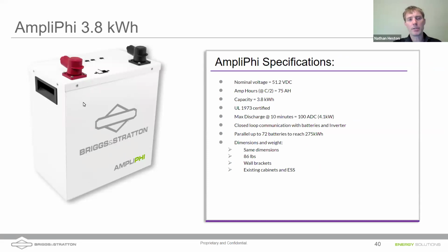This is our AmpliPHI battery. It's got that more sophisticated communicating BMS that's in there, allowing you to communicate with compatible equipment like a Solar inverter or a Briggs Stratton inverter. It's got the integrated breaker as well, and this battery comes again in the same overall capacity, 3.86 kilowatt hours at standard temperature.